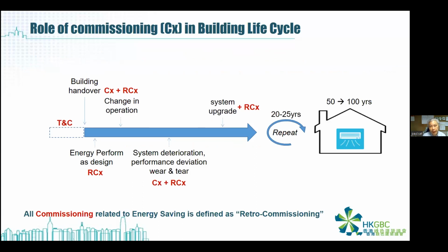So we can go back into the building life cycle. In the building life cycle, we do so many commissioning activities, no matter whether it's retro-commissioning or commissioning. Before the building is built, after construction it will be handed over to the facility manager, with testing and commissioning in order to test the system's functionalities and performance. After that, the building is handed over to the facility management, or we call them the operators. When the operators receive the building, first of all, if the building is a green building, they need to know the energy performance of the systems. If the energy performance of the systems is not very good, they need to do some retro-commissioning in order to fine-tune the performance of the building to meet the design of the green building. That is the first part.